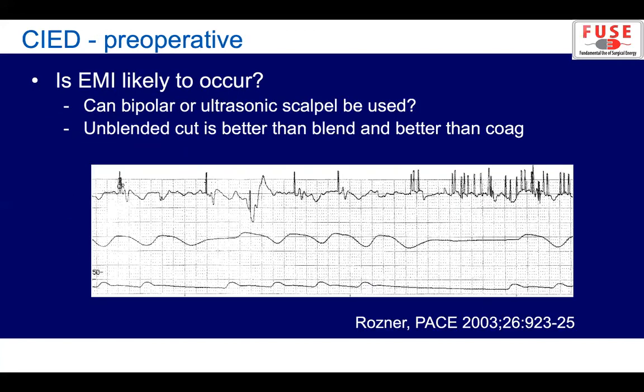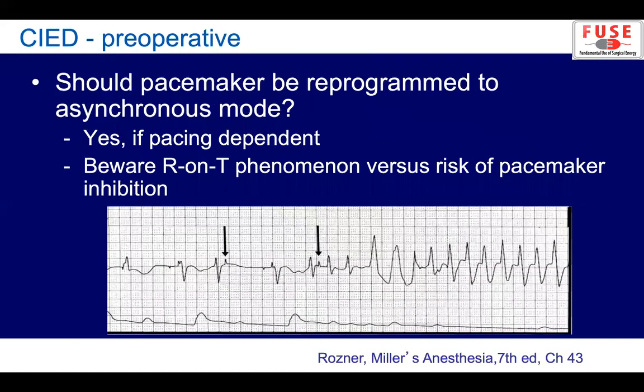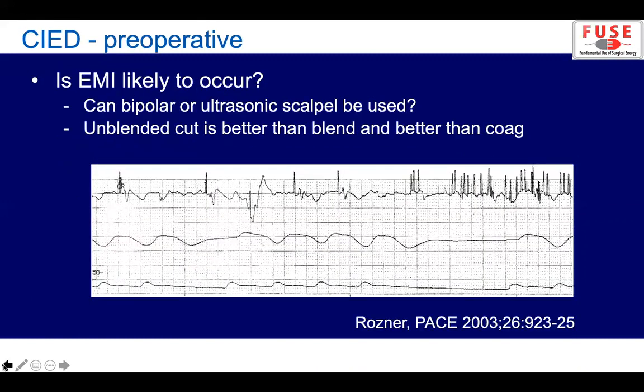Then you need to decide whether EMI is likely to occur. Can a bipolar or ultrasonic scalpel, something like a LigaSure or Gyrus, be used instead of monopolar devices? If you need to use a monopolar device, then can unblended cut be used, which is better than blend and better than coag when it comes to interfering with CIED devices? Basically, when you're talking about the choice of mode, unblended cut is continuous, easier for the device to filter, and lower voltage, and that's the benefit of that mode.